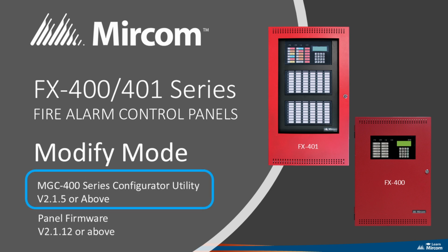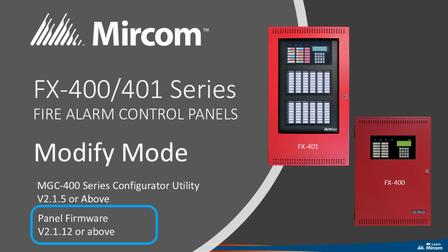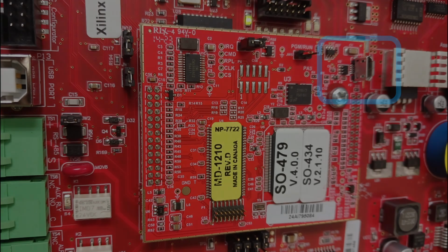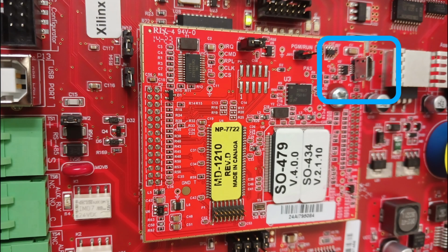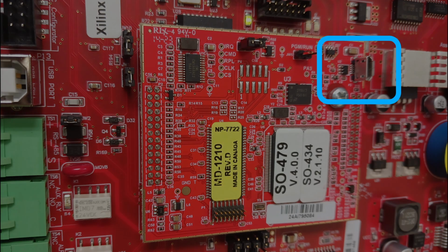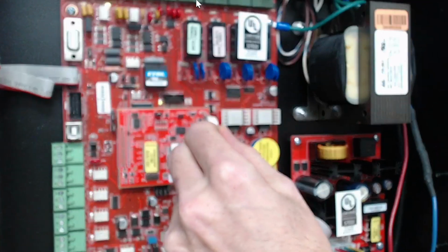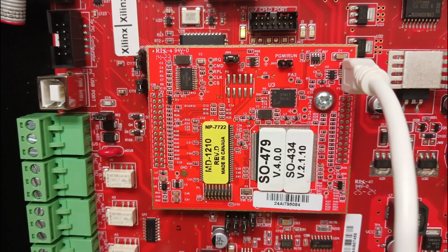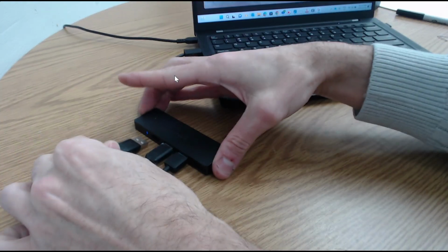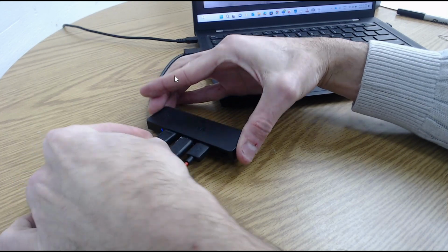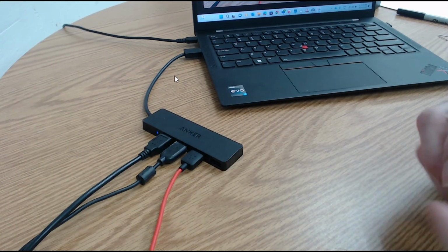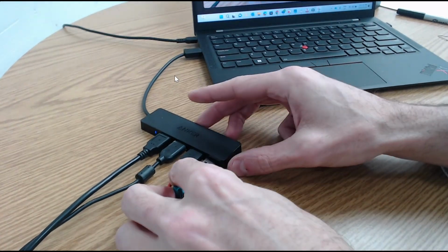You'll need to have the software configuration application version 2.1.5 or above, and the panel requires firmware version 2.1.12 and above. Locate the micro USB port on the core board. Connect to the panel with a USB micro cable that supports data transfer. Plug the other end of the cable into one of your laptop's USB ports. Make sure you have a valid USB security key plugged into your laptop also.